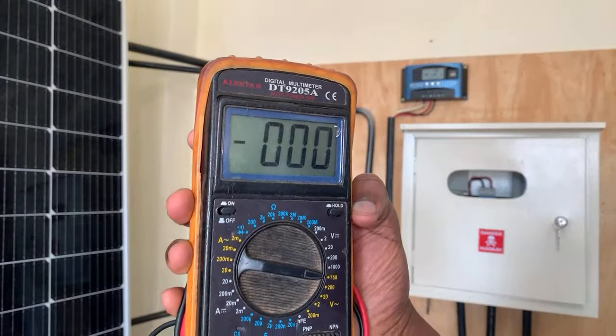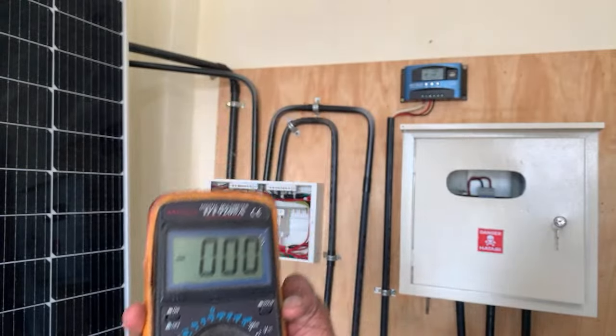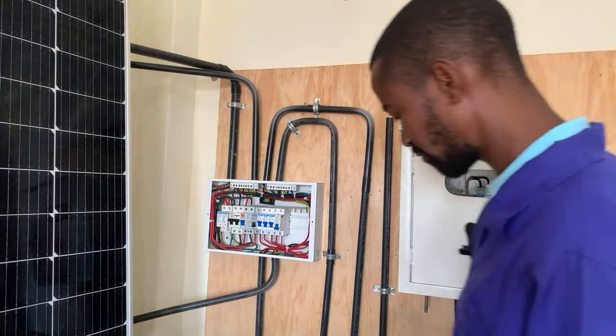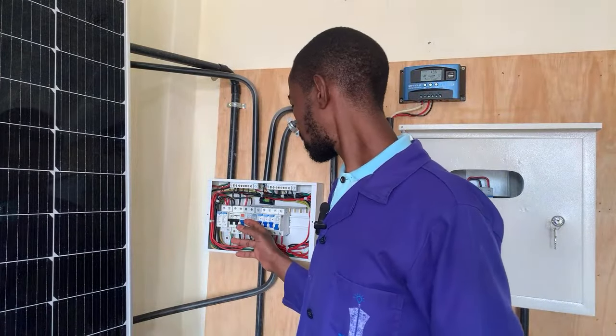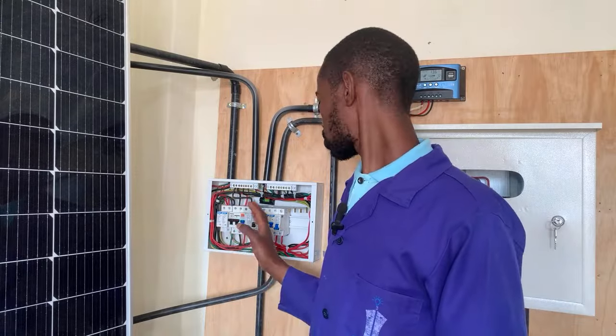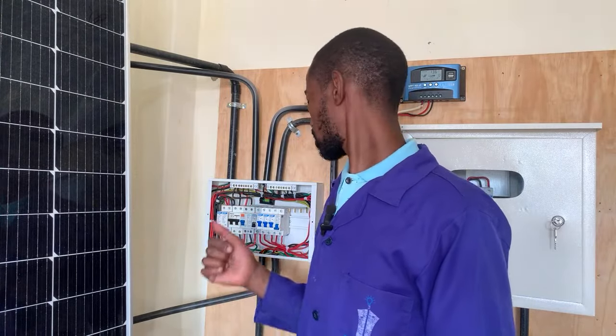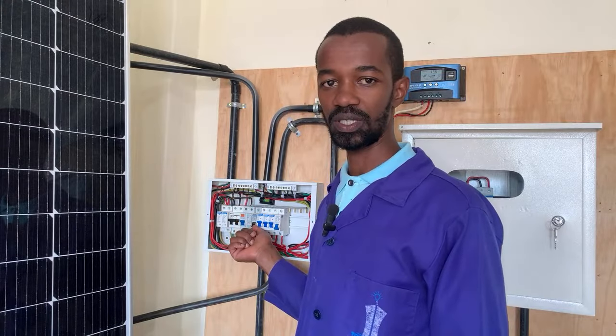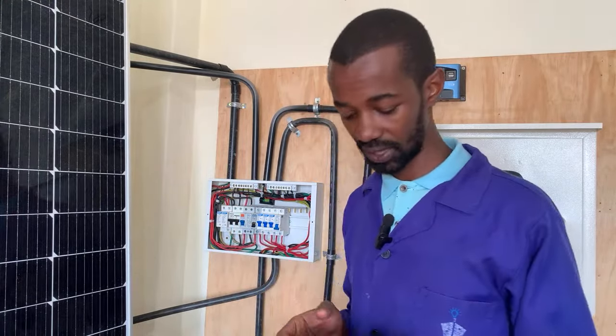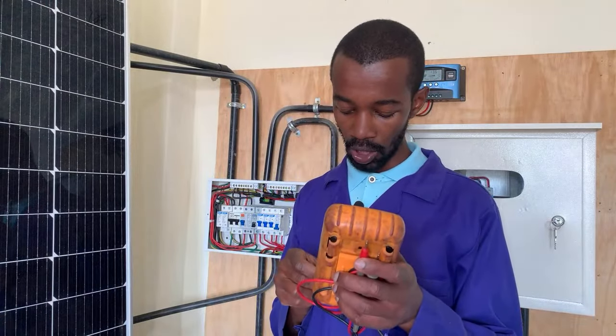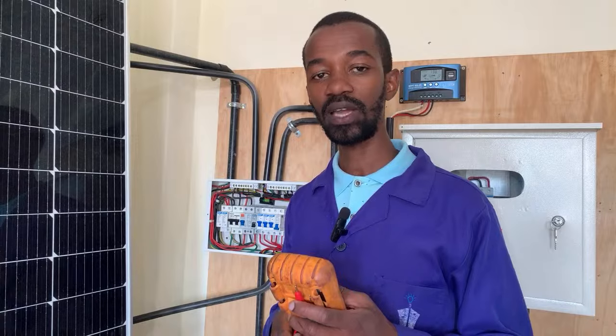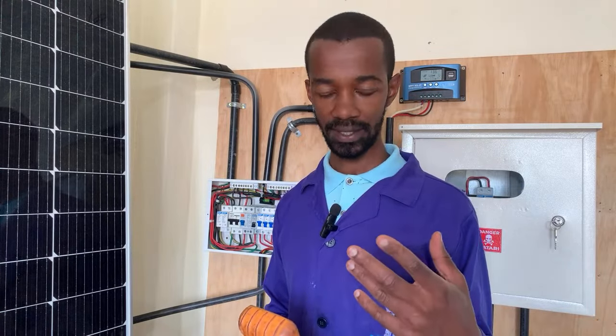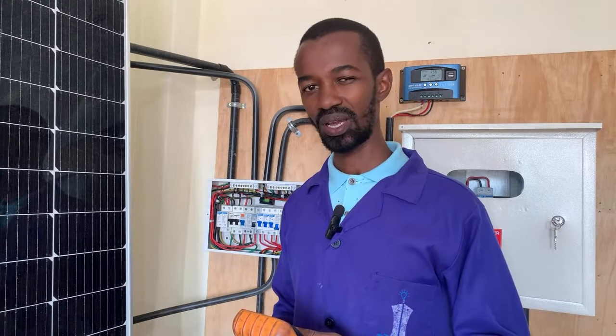Also, let's say someone says they have an issue with their microwave, or probably the instant shower head is not working, and they have already confirmed that there is a circuit breaker that has tripped. Now, what you need to do is to first of all visit that place with your meter, and then you will start with that specific appliance that was connected. Let's say it is an electric cooker that is not working. So you will first of all unplug it from the socket. Once you unplug it, then you will be able to troubleshoot what could be the problem.